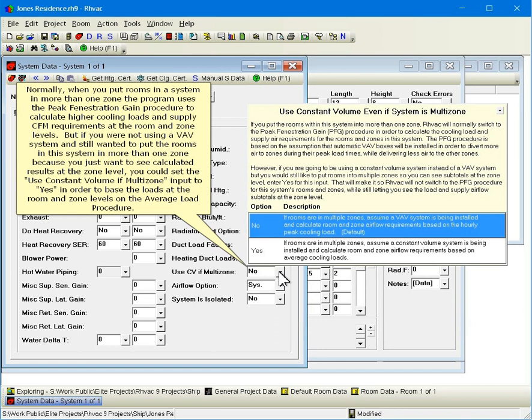Normally, when you put rooms in a system in more than one zone, the program uses the peak fenestration gain procedure to calculate higher cooling loads and supply CFM requirements at the room and zone levels. But if you were not using a VAV system and still wanted to put the rooms in this system in more than one zone because you just wanted to see calculated results at the zone level, you could set the use constant volume if multi-zone input to YES in order to base the loads at the room and zone levels on the average load procedure.